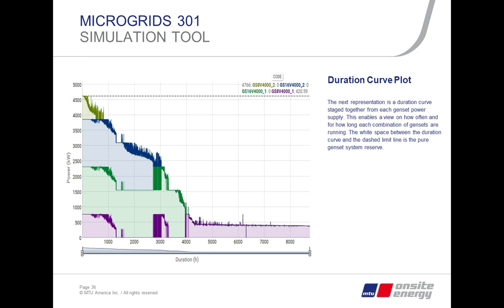So once we get into the microgrid control setup, we'll be able to levelize the run hours between that brown unit and the purple unit at the bottom, to make sure we're not overstressing it, and to push that big overhaul as far out as possible, levelizing the run hours across the engines.